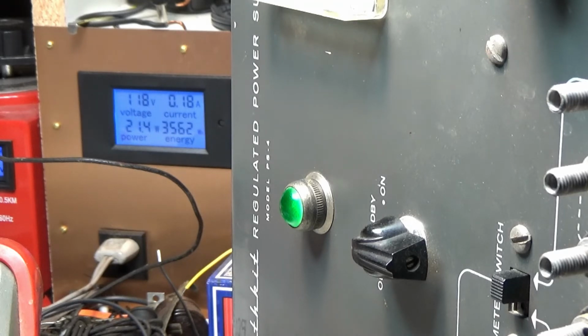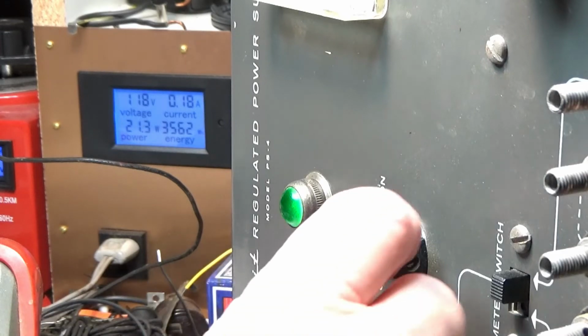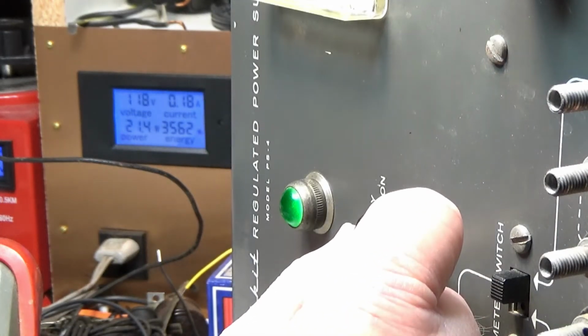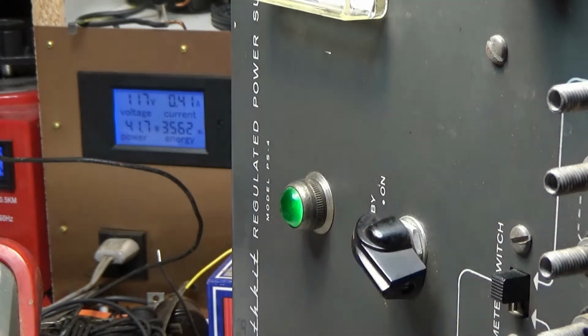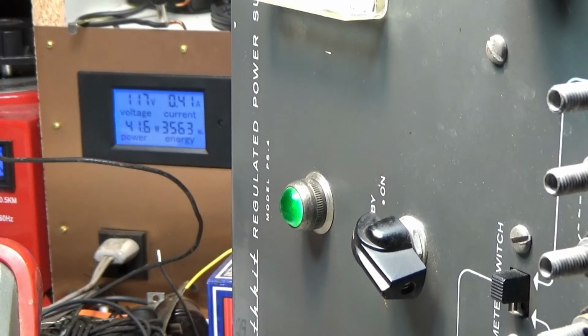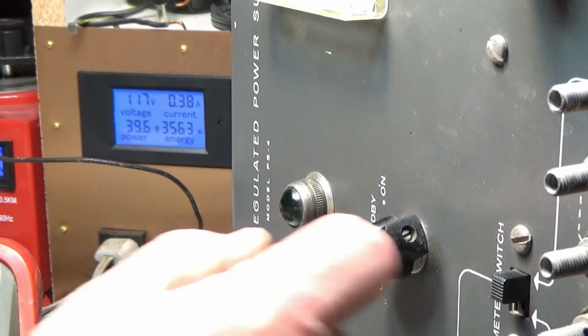So something's automatic. There's a bad capacitor. Something's bleeding voltage to ground. Look at that, look at that jump. If it was a 1 amp fuse, we're almost a third of the way there without even having something on the front of it. Got to be careful.